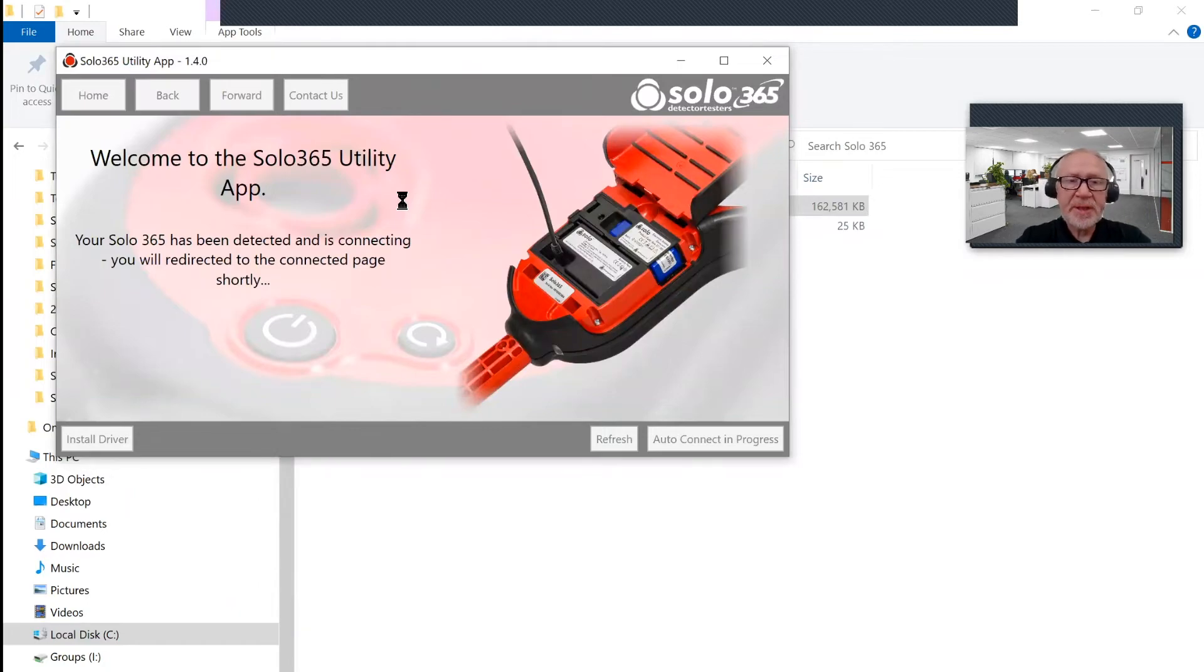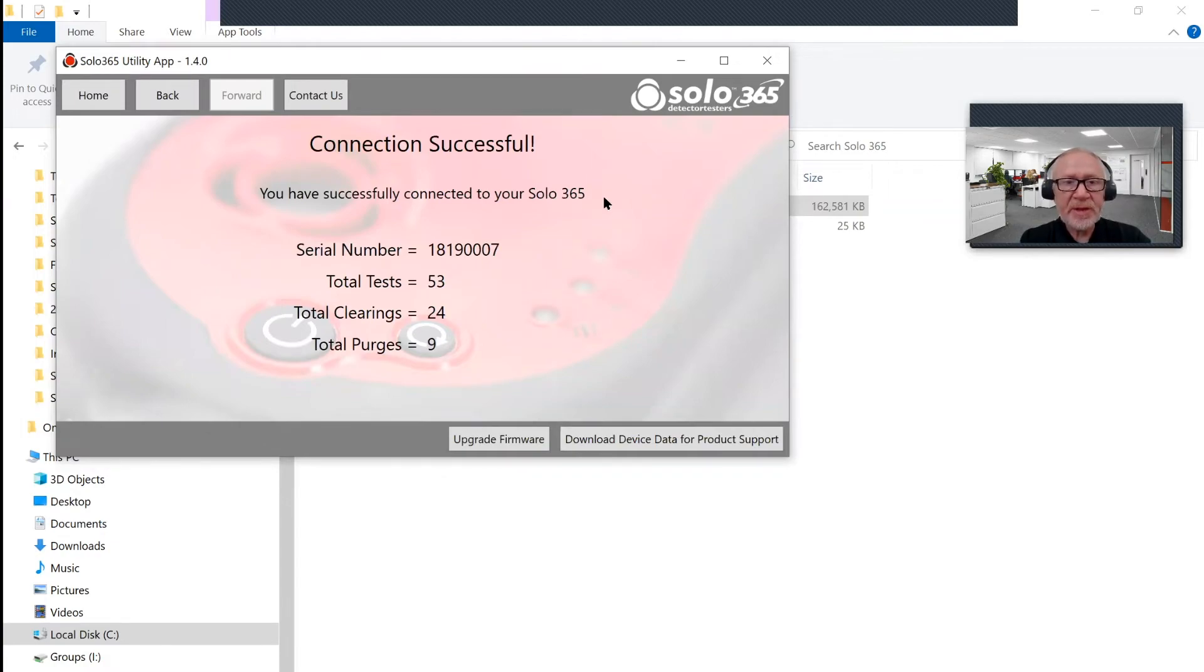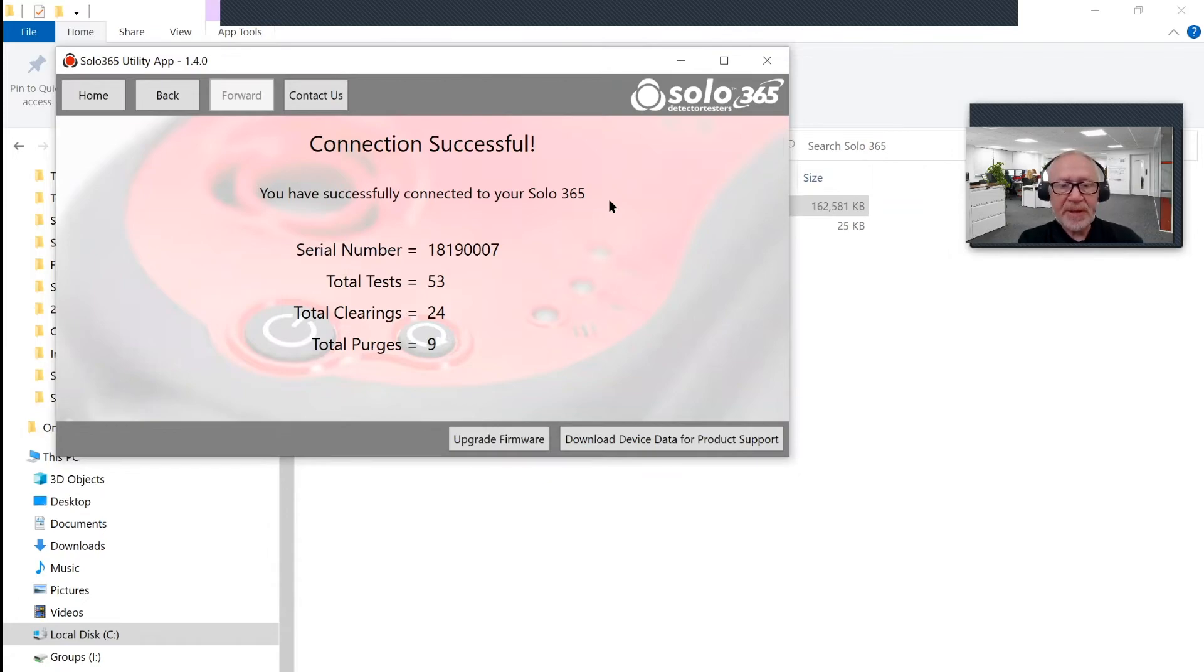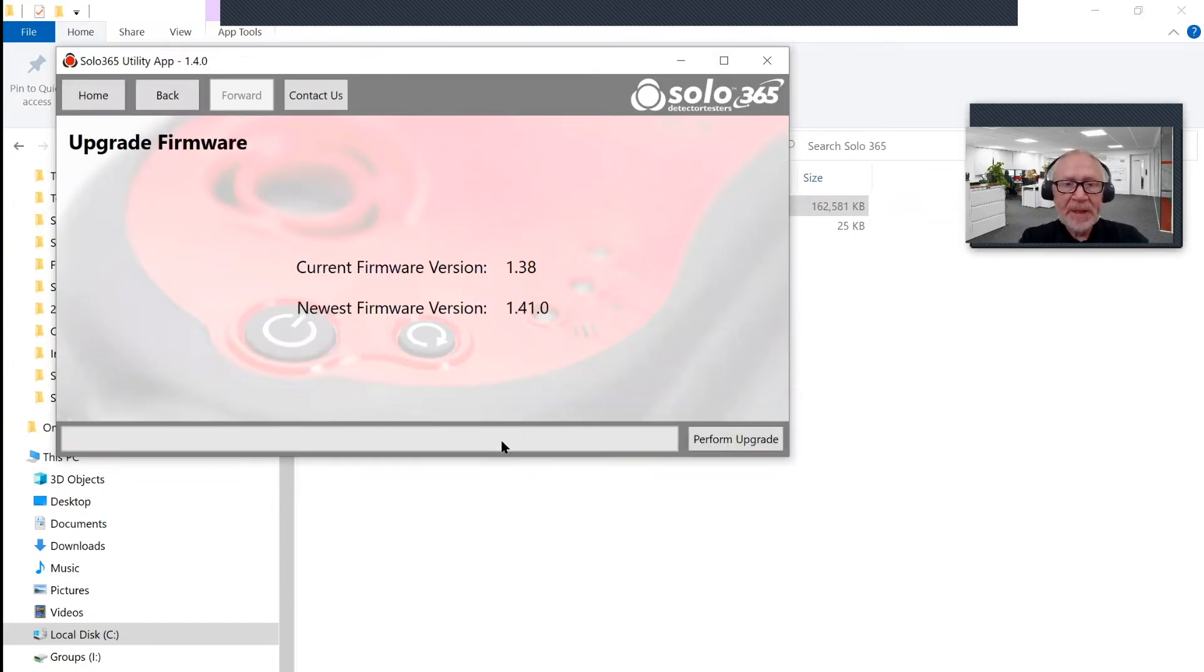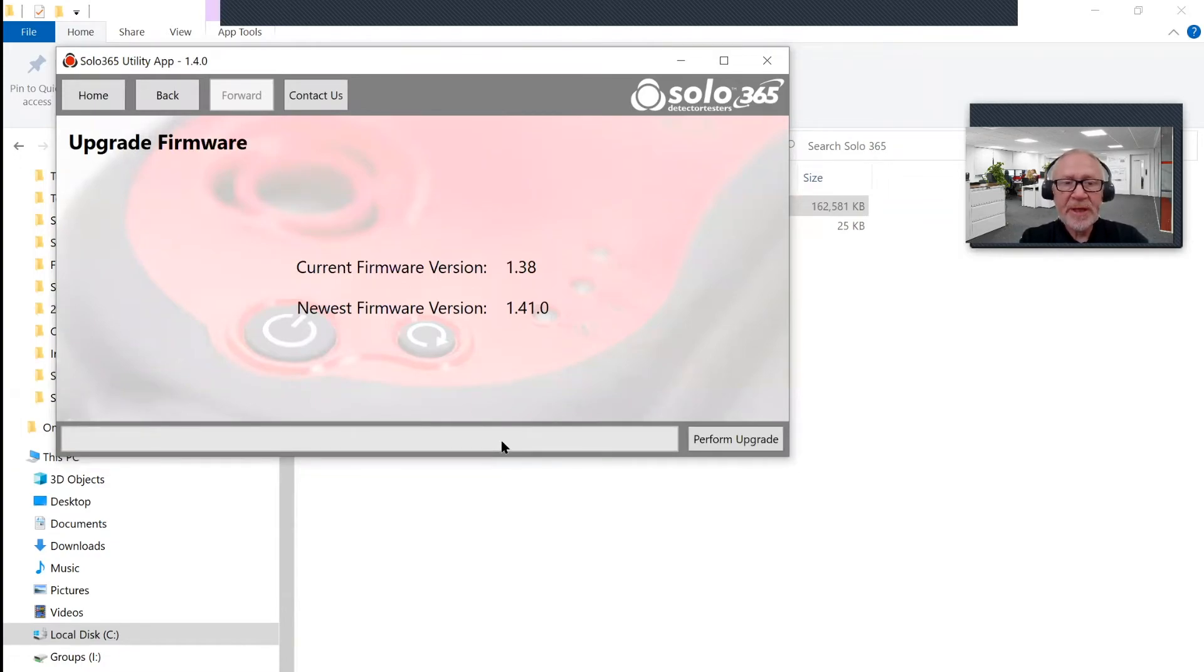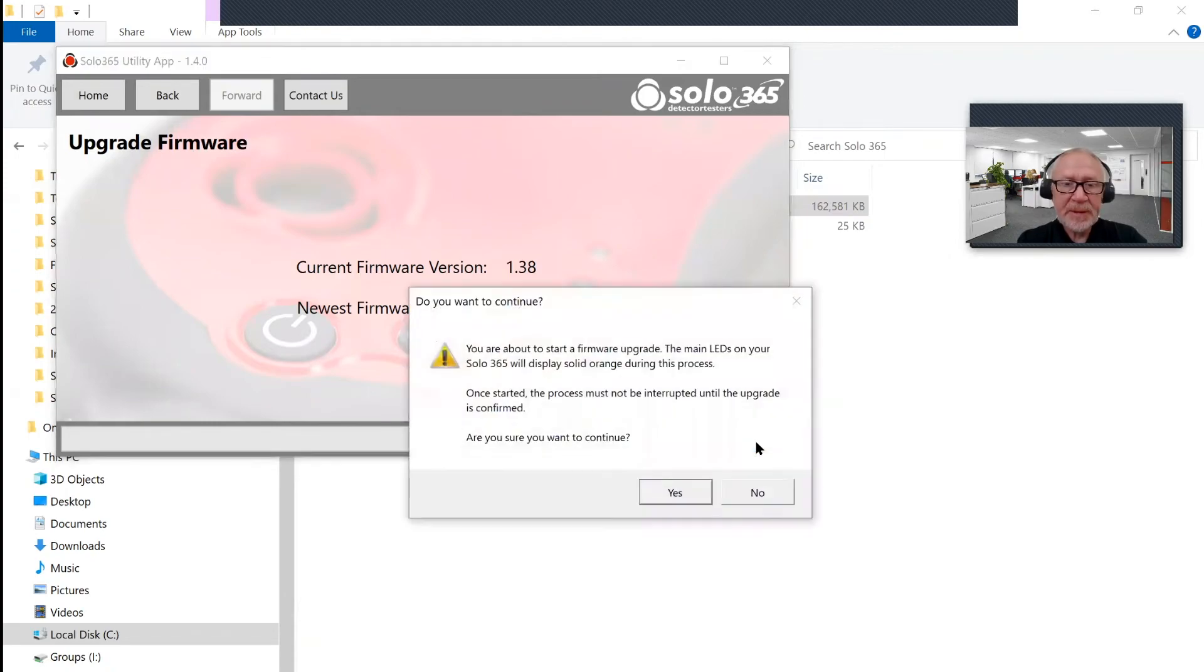It just takes a few seconds to communicate with the Solo 365. And there we have a successful connection to the Solo 365, giving a serial number and other details about that particular unit. Down the bottom there, there's a button that says upgrade firmware. We click on to there. And this is where it tells us what the current firmware version is, which is 1.38, and the newest firmware available is 1.41. To perform the upgrade, click on the upgrade button.